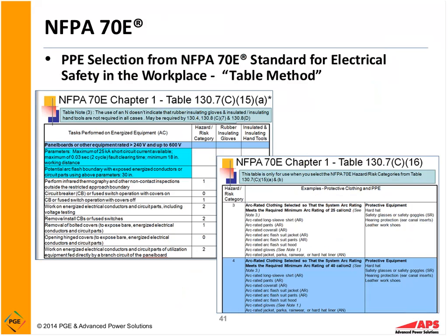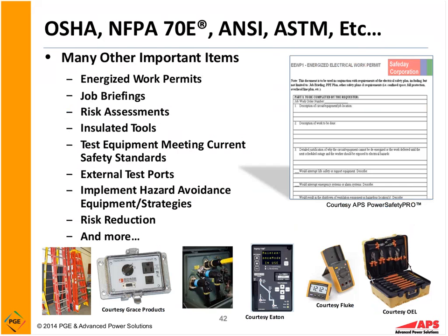So if we don't have a study done, if we haven't had someone come in and actually calculate the incident energy levels, we can use what's called the table method in NFPA 70E. Again, I would suggest if you don't have a copy, you can view NFPA 70E free online at nfpa.org. If you go on to nfpa.org, you can look at the NFPA 70E standard free online. You can't print it or copy it, but you can look at it.